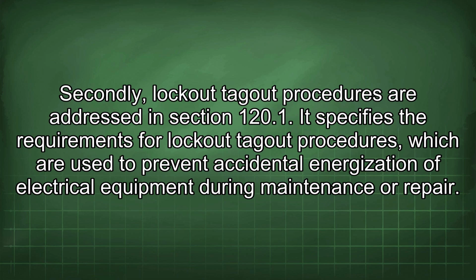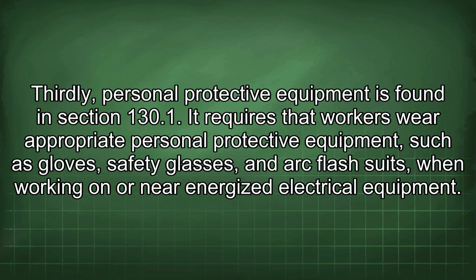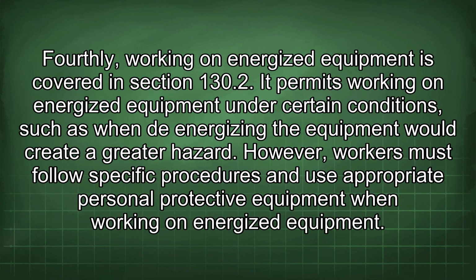Secondly, lockout-tagout procedures are addressed in Section 120.1. It specifies the requirements for lockout-tagout procedures, which are used to prevent accidental energization of electrical equipment during maintenance or repair. Thirdly, personal protective equipment is found in Section 130.1. It requires that workers wear appropriate personal protective equipment such as gloves, safety glasses, and arc flash suits when working on or near energized electrical equipment. Fourthly, working on energized equipment is covered in Section 130.2.